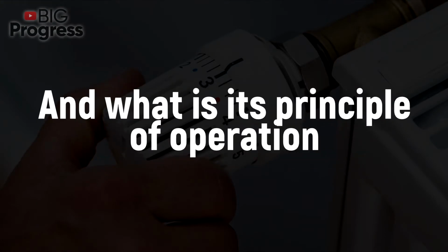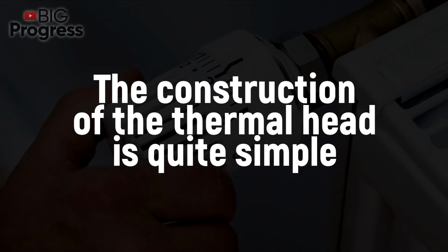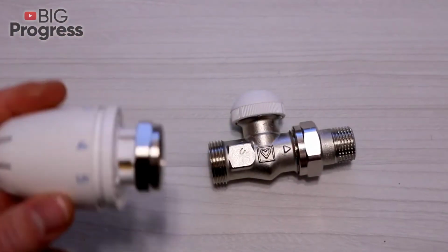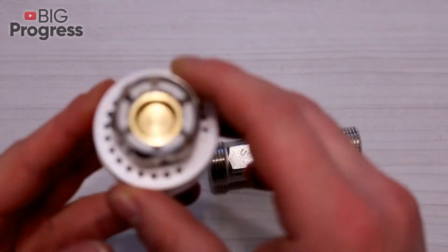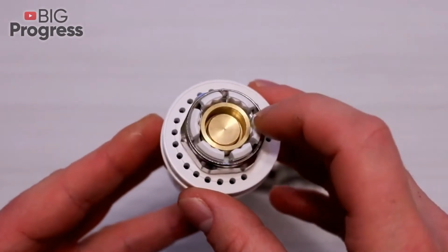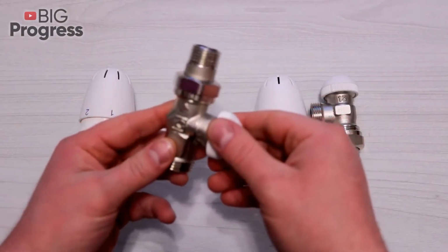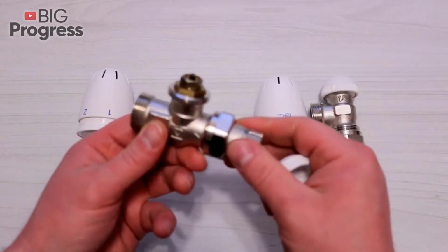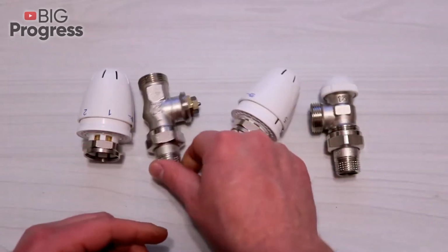Next, let's see how the thermal head is arranged inside and what is its principle of operation. The construction of the thermal head is quite simple. The thermostatic regulator has a body, special bellows with a filler that responds to changes in air temperature, a stem of the thermostatic element, and a connecting mechanism that allows the thermostatic head to be fixed on the thermostatic valve. And here's how it works.